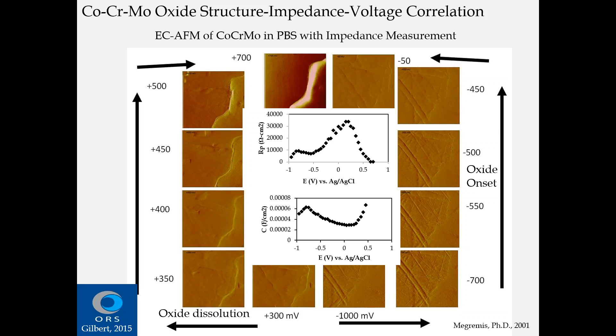And then if you go back to the bottom, starting at +300 and going onward, you can see how that oxide film suddenly changes its topography, its morphology. And then as we get up into the 400 and higher range, you begin to see this active corrosion taking place. That's corresponding to how the resistance of that oxide film varies with voltage. So this rising impedance corresponds with how the oxide film first starts and increases its thickness, and then begins to fall down again as that oxide transitions into this plus 300 and higher range. And so this correlation between the oxide film morphology and its properties is very, very good and indicates the behavior of cobalt chromium across the range of voltages in phosphate buffered saline.